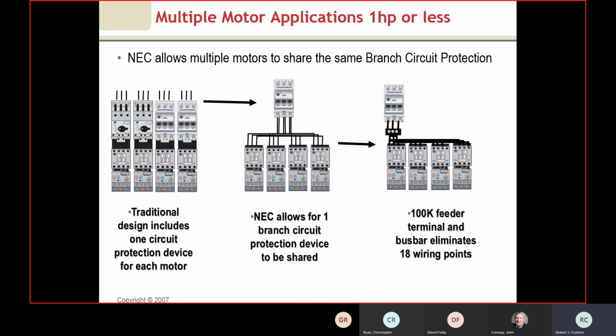So here is a multi-motor application. To the left, you notice this is the way we typically would wire. It is very wire intensive and very time intensive to wire those together. NEC allows us to do one branch circuit for many starters and multiple motors. And all the way to the right, we've optimized that even more by using the 100K feeder. These are the smaller units. The 100K is a smaller version below the 100C units. So notice the wiring here, the minimized amount of wire that needs to be cut and stripped. We just take the compact bus bar and wire it into these units.